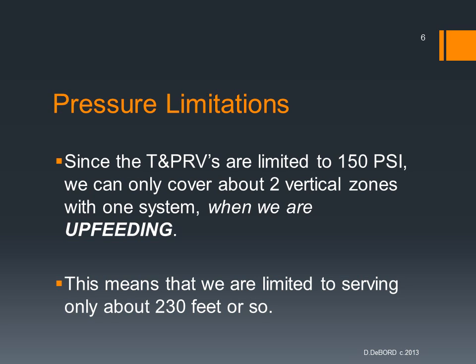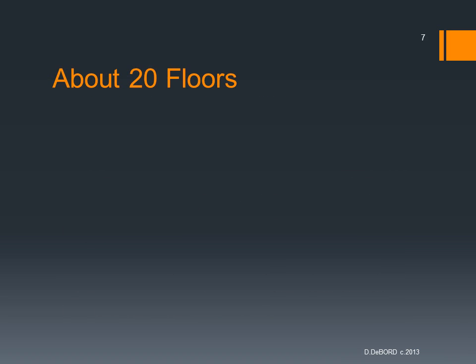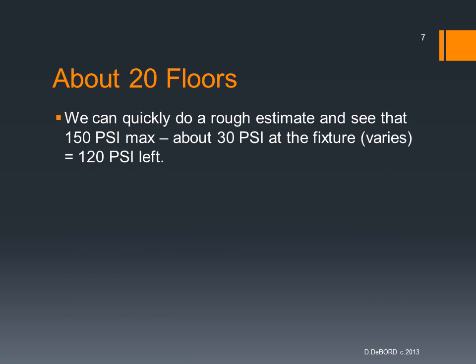So since the T&P valves are limited to 150 psi, we can only cover about 2 vertical zones within one system. But you know what? That's only for upfeeding. And what does that mean? Well, for one thing, it means that we're limited to serving only about 250 feet or so. And that's about 23 floors.